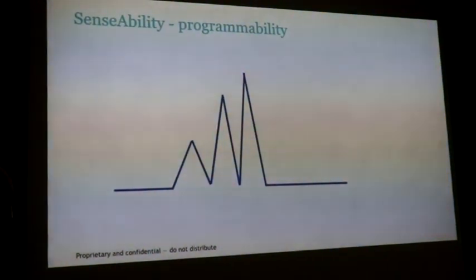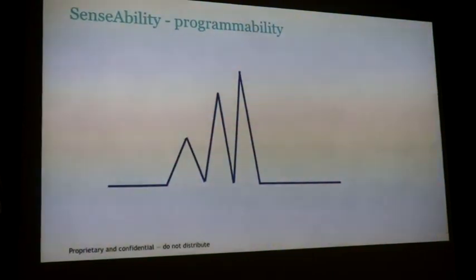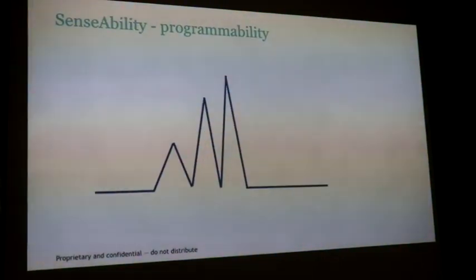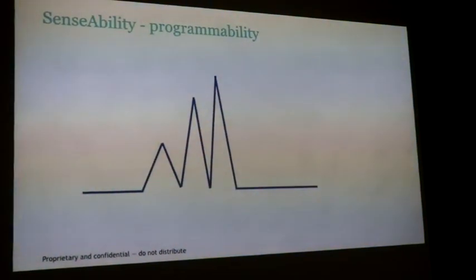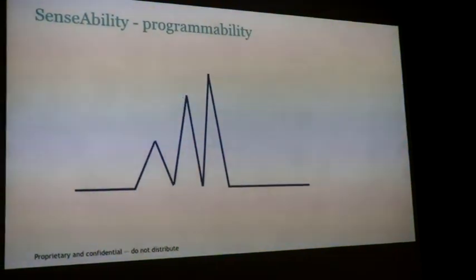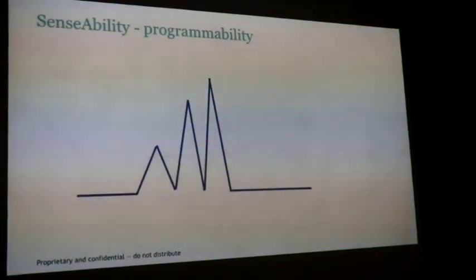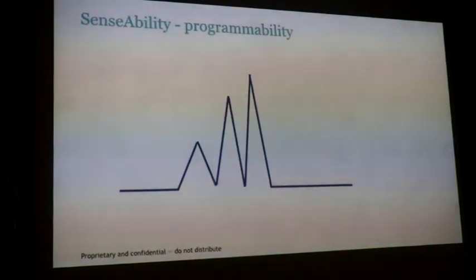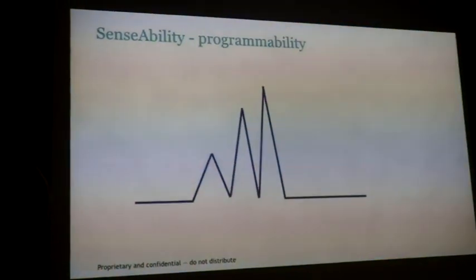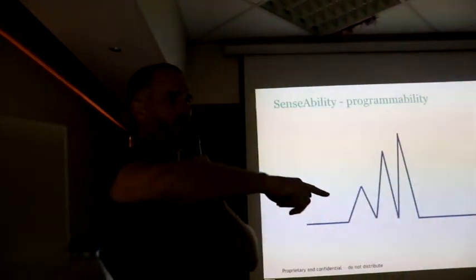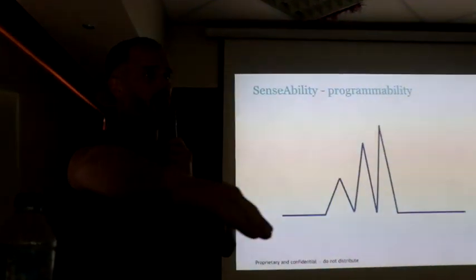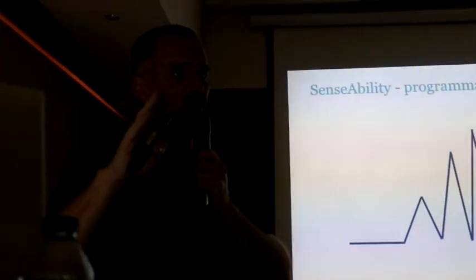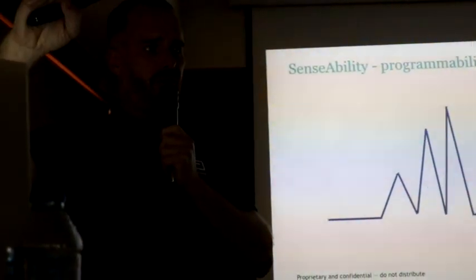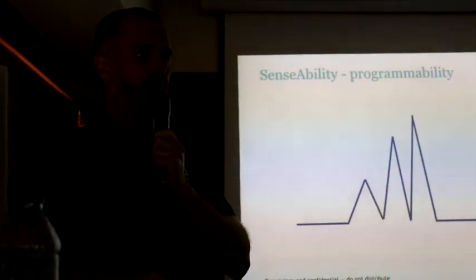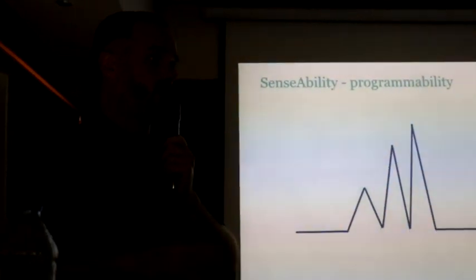So on our atrial leads we often like to use automatic sensitivity because it provides much better detection for AF. In our ICDs and CRT-Ds, all channels, the atrial and the ventricular channel, use automatic sensitivity because we're trying to detect VF. VF goes from a big signal in sinus rhythm to very, very small signals, and we need to track those down, because typically after about 20 or 30 seconds those signals in VF will be less than 2.5 millivolts. So we need to get to very high sensitivity with our defibrillators.